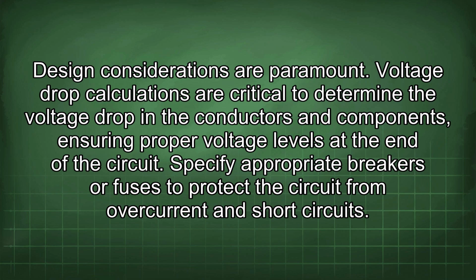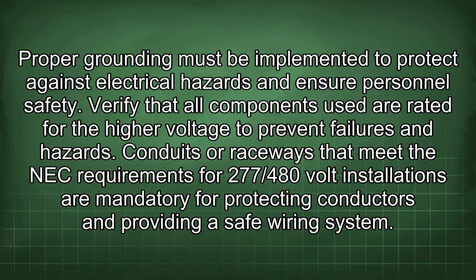Voltage drop calculations are critical to determine the voltage drop in the conductors and components, ensuring proper voltage levels at the end of the circuit. Specify appropriate breakers or fuses to protect the circuit from overcurrents and short circuits. Proper grounding must be implemented to protect against electrical hazards and ensure personnel safety. Verify that all components used are rated for the higher voltage to prevent failures and hazards. Conduits or raceways that meet the NEC requirements for 277/480 volt installations are mandatory for protecting conductors and providing a safe wiring system.